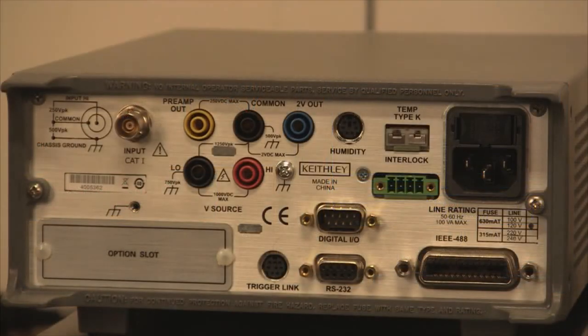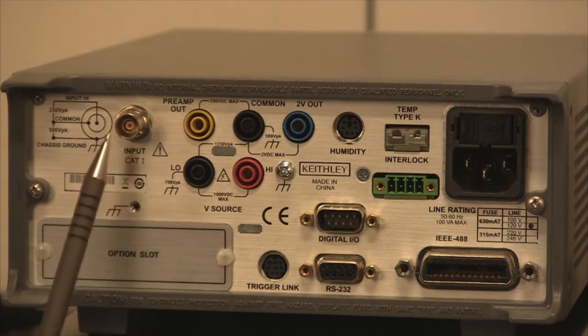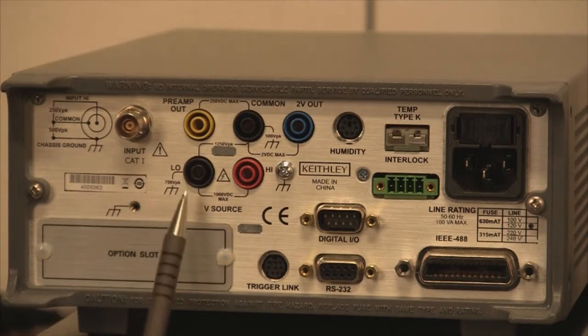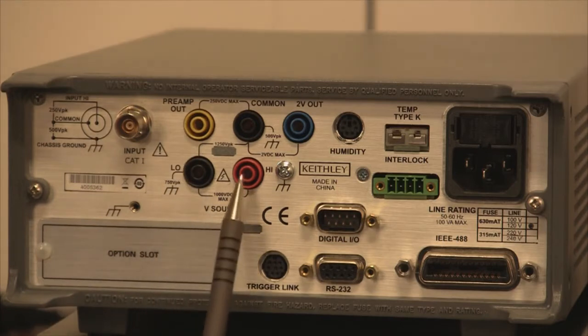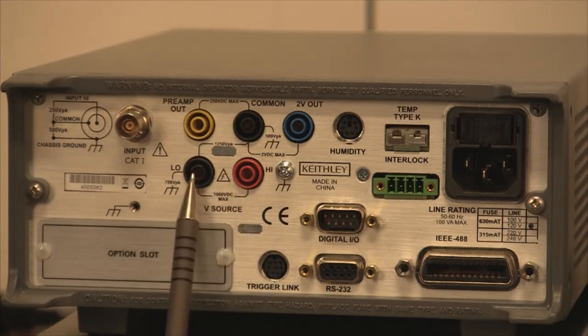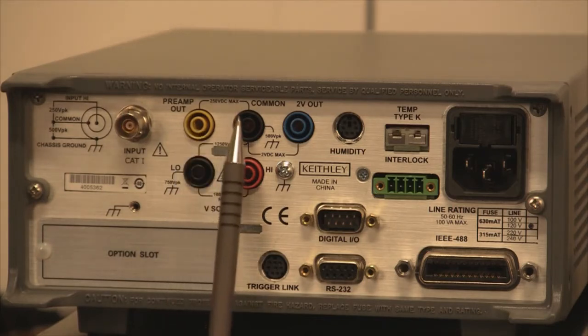Here is the rear panel of the 6517B, and I thought we'd go over it to go through the connections so you get that straight. In the upper left-hand corner, you'll see the three-lug triax input. You'll see the voltage source banana jacks, high and low. And what we're doing with the scope, we're measuring from preamp out to common.